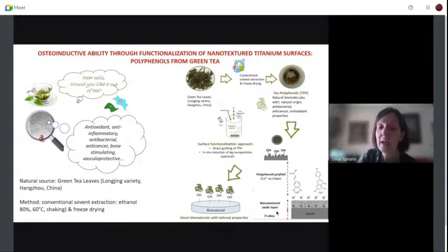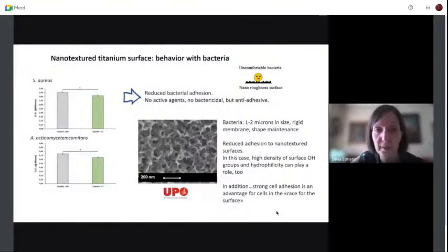Yes, yes. Concerning just the nanotopography, so this surface, we performed a sort of simulation of the implantation procedure by using a bovine bone and by using just the same equipment for a human usual implantation. And we observed that the nanotopography is resistant to the friction applied during the implantation.